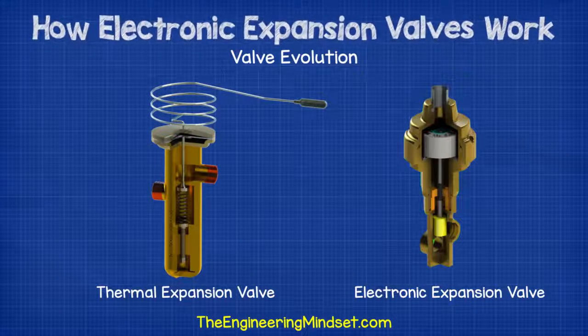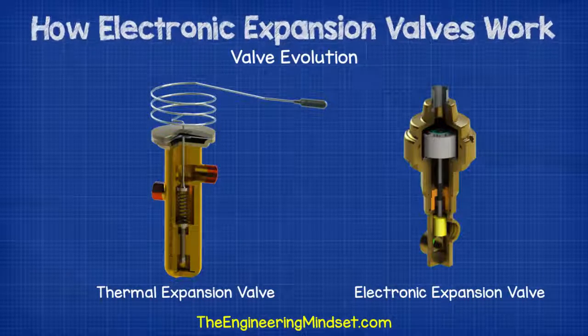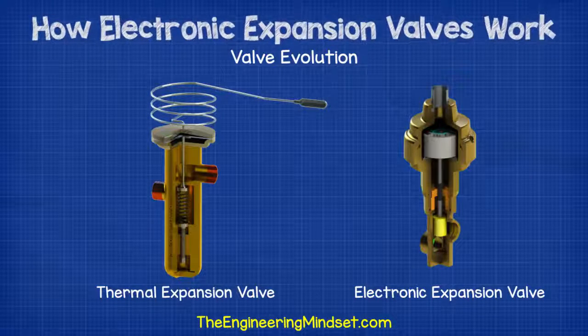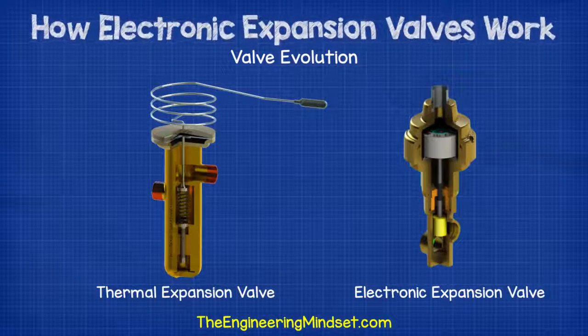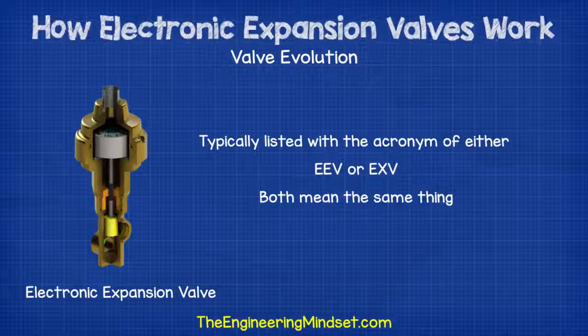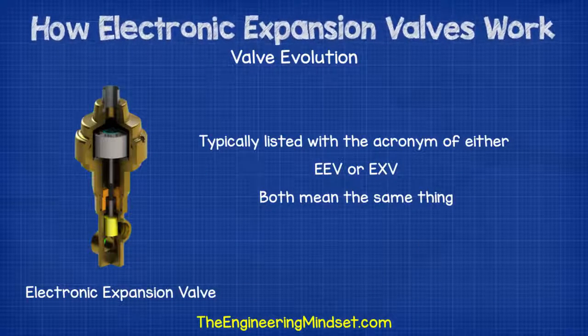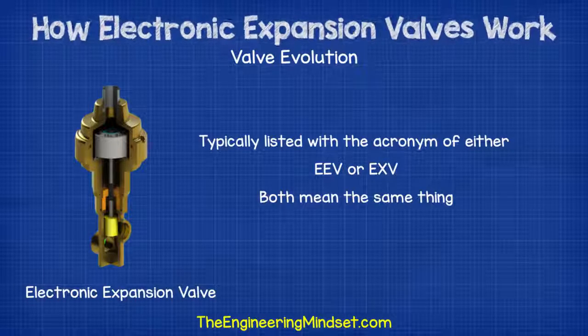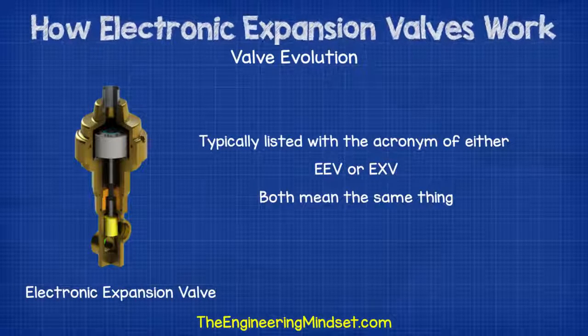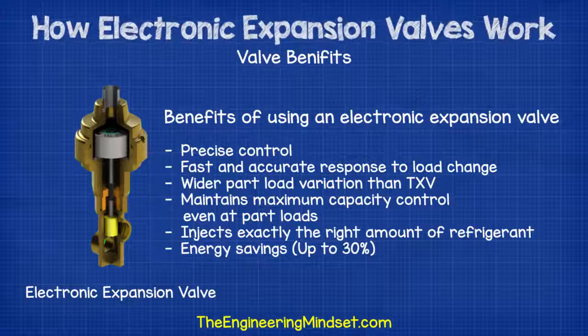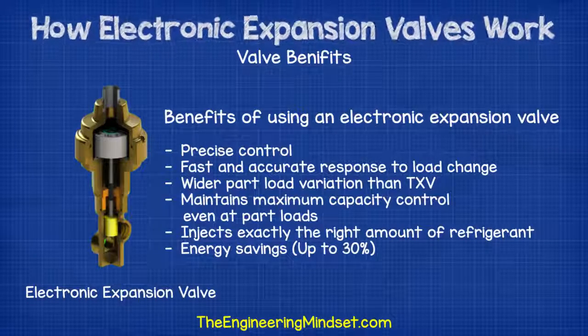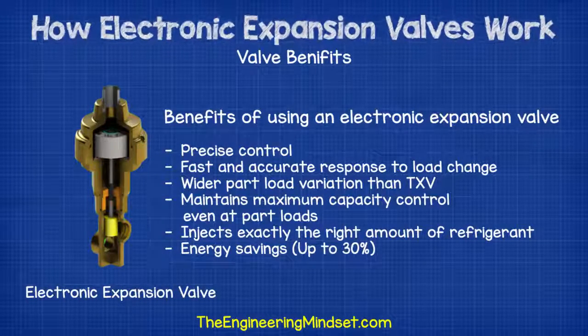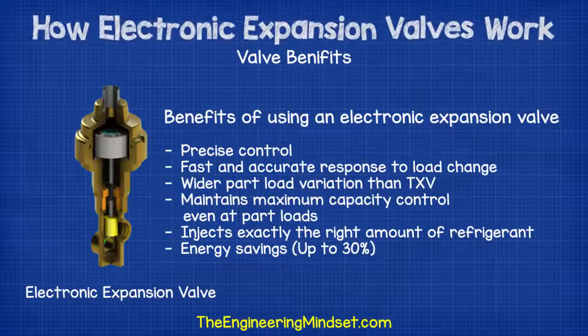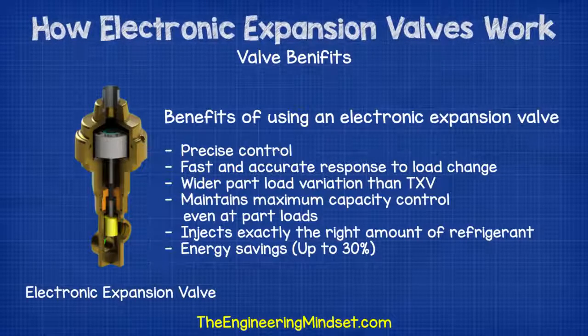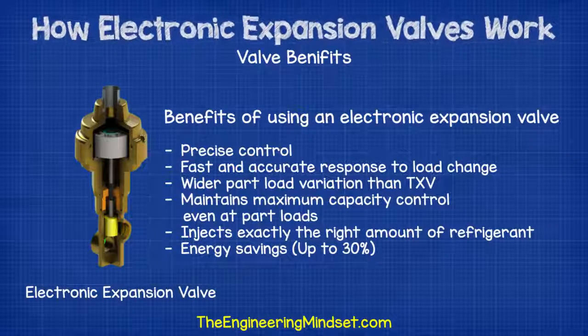Electronic expansion valves are an evolution on the thermal expansion valve. They are much more sophisticated and allow the refrigeration system to operate much more accurately and efficiently. You'll usually see the electronic expansion valves listed with the acronym of either EEV or an EXV. They both mean the same thing, it just varies by manufacturer. There are many benefits to using an electronic expansion valve, and I've listed some of the main points on screen now. The focus though is usually that by using an electronic expansion valve, you're going to reduce the energy consumption of the refrigeration system as well as gaining much better performance.